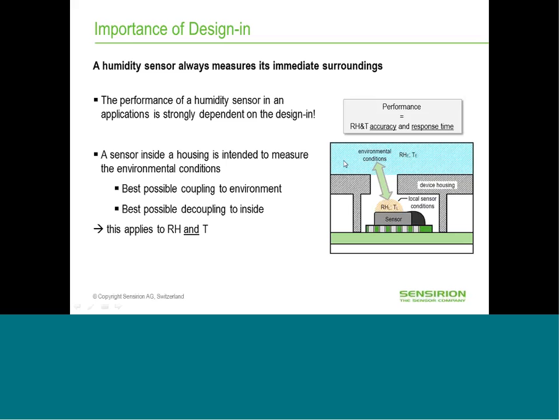In order to achieve the optimal performance, the design in has to be really well done, because the best humidity sensor with the best performance does not perform well in the application if the design is bad. When I talk about performance here with the design topic, I mainly talk about accuracy and response time - how quickly the sensor reacts to a change in environmental conditions.